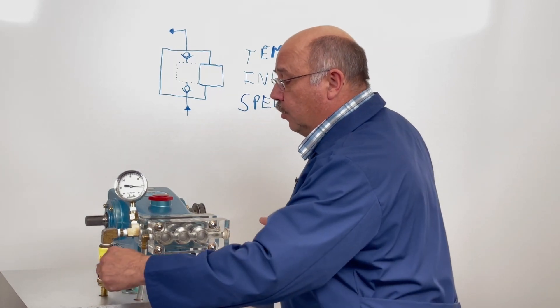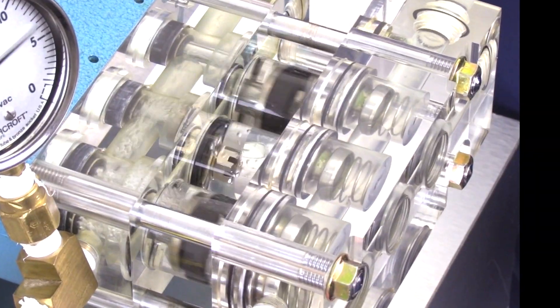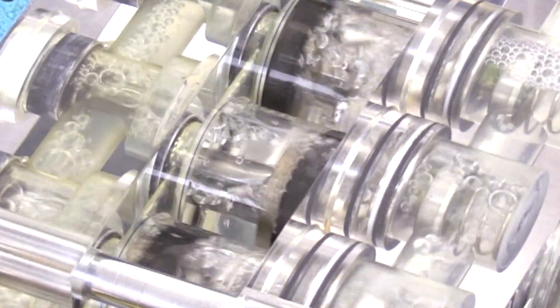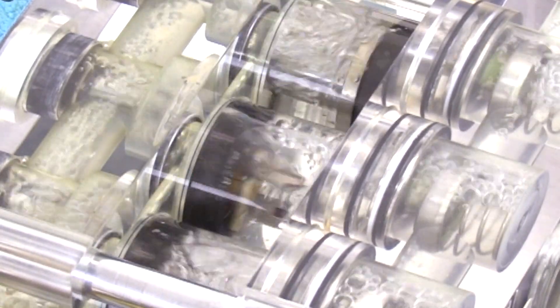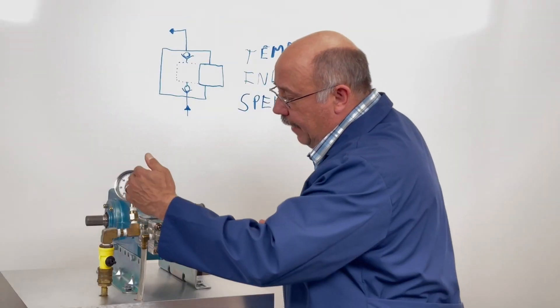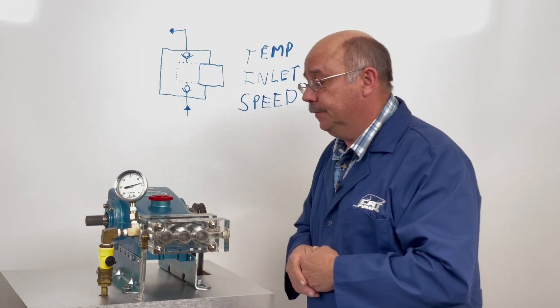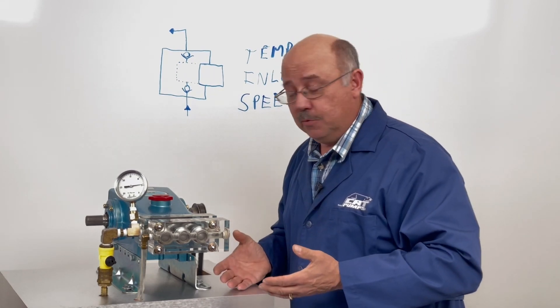As we start to restrict this inlet we can start to see the bubbles forming and the water separating and collapsing and getting this higher vacuum going. And of course then the vacuum goes up higher as well and now we're in a cavitation state on this pump. So this is what you want to avoid.